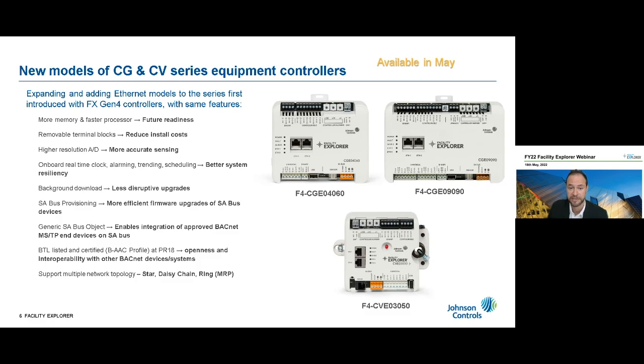So you can guess it's an IP controller because it has an E and it has 9 inputs and 9 outputs, so a total of 18 points. At the bottom, we have a picture of the CVE 0305. So it's a C for controller, V for VAV box, and it is an 8-point controller with 3 inputs and 5 outputs. So we're gonna dive more into the details of those controllers in the next slide.